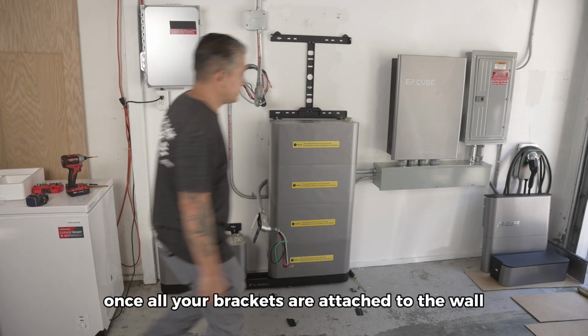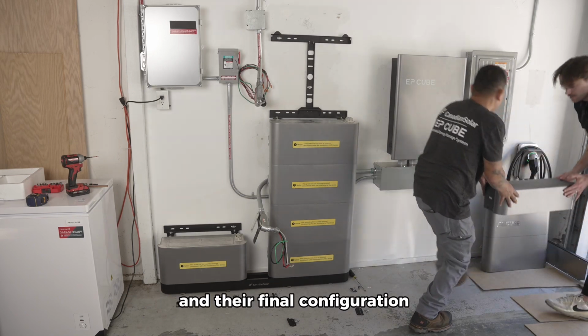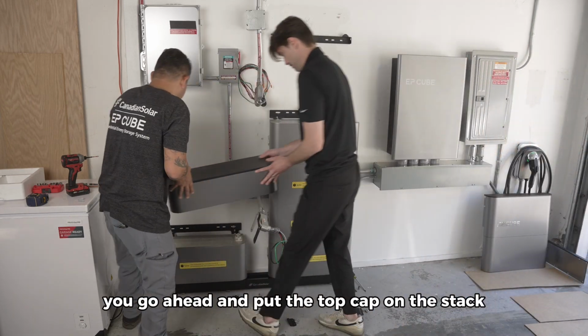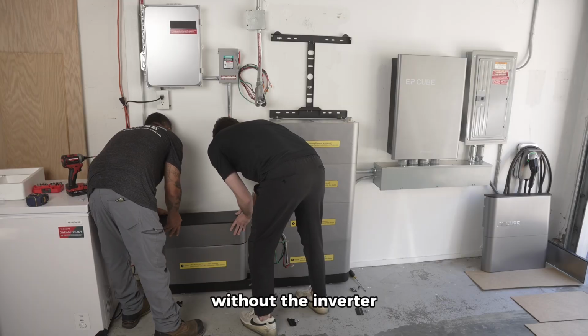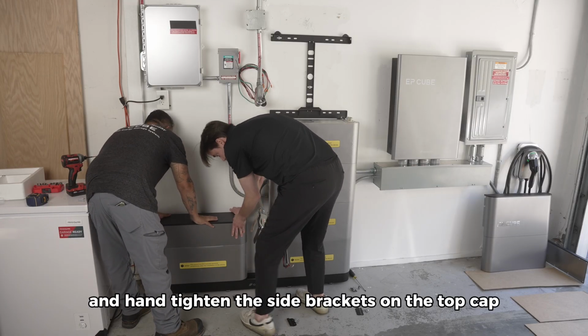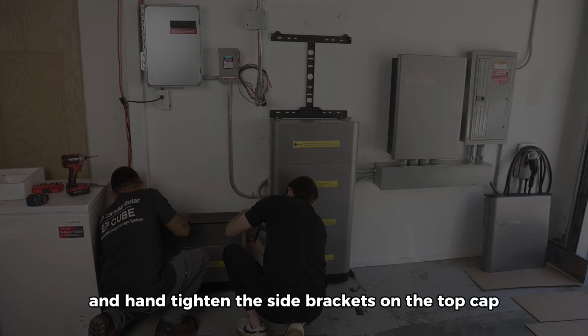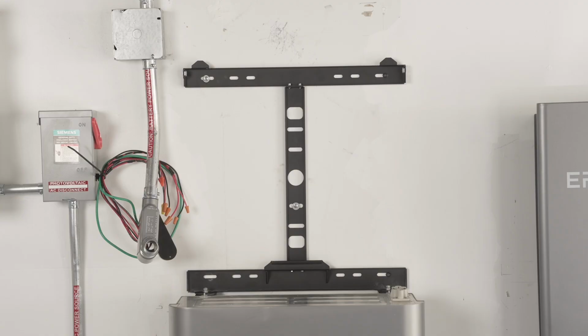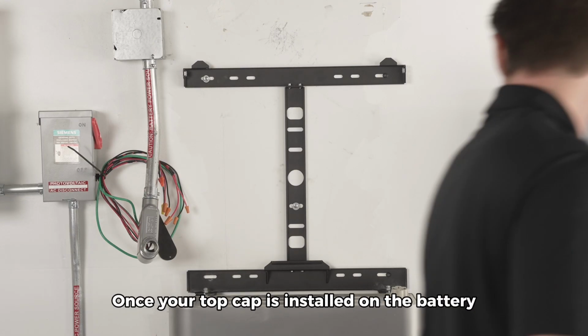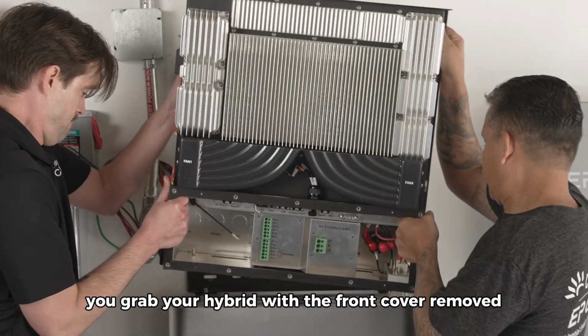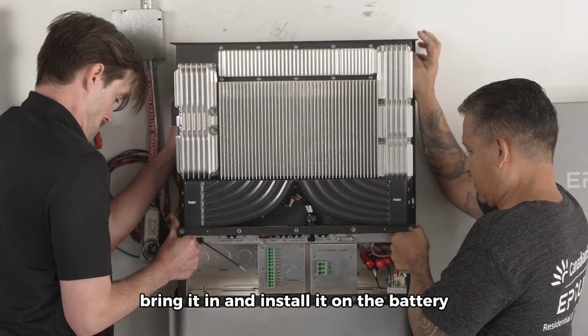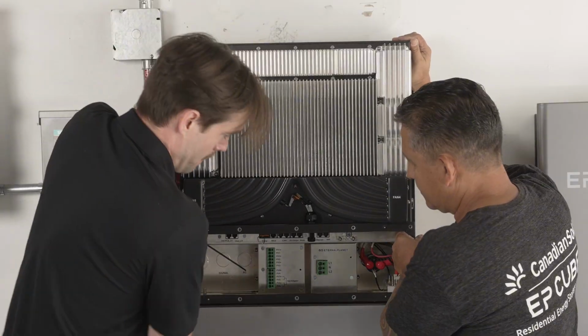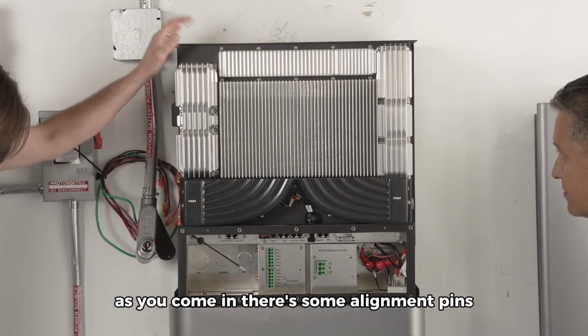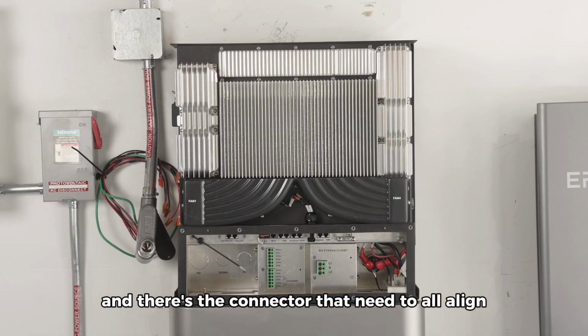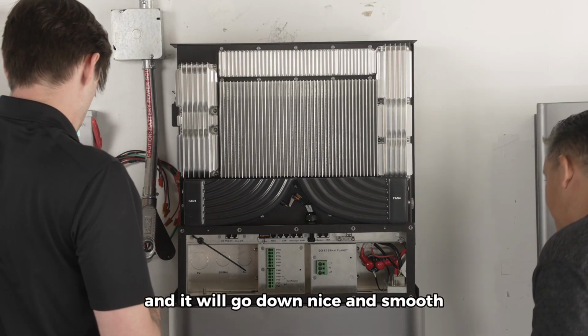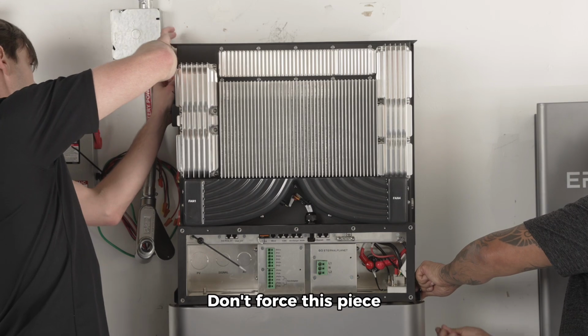Once all your brackets are attached to the wall in their final configuration, you go ahead and put the top cap on the stack without the inverter, and you'll want to go ahead and hand tighten the side brackets on the top cap. Once your top cap is installed on the battery, you grab your hybrid with the front cover removed, bring it in and install it on the battery. As you come in, there's some alignment pins and there's the connector that need to all align, and it will go down nice and smooth once everything's in alignment. Don't force this piece.